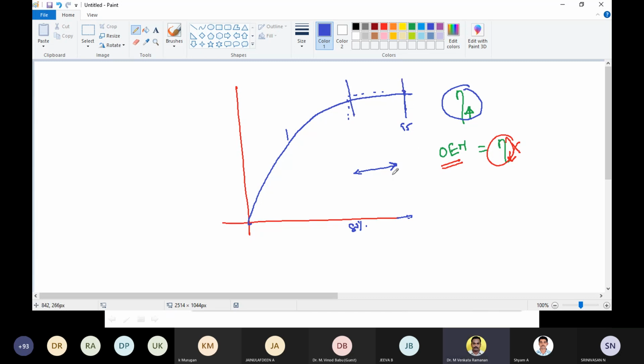If you choose a high capacity motor for a lower load, you will be operating the motor at part load, and automatically your efficiency would be lower. This leads to inefficient operation. But the same motor, if loaded to a higher level, will operate at the highest possible efficiency. So ultimately, we have to choose the load appropriately and have it done.